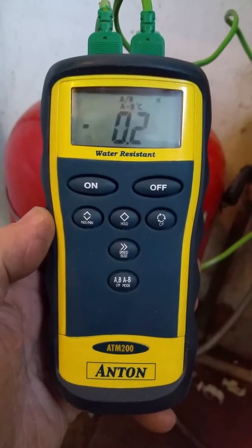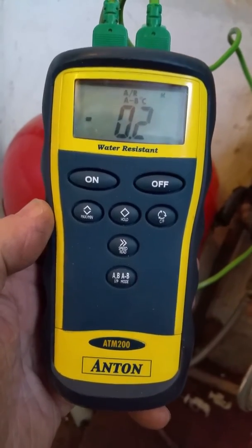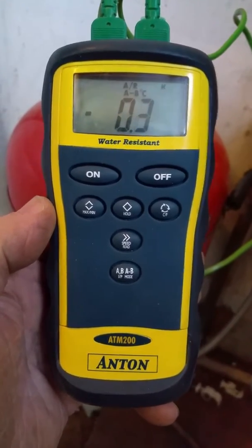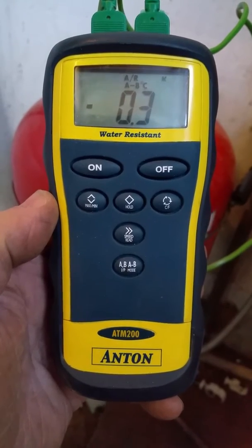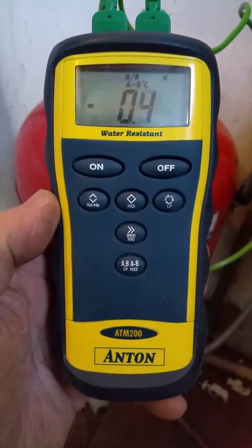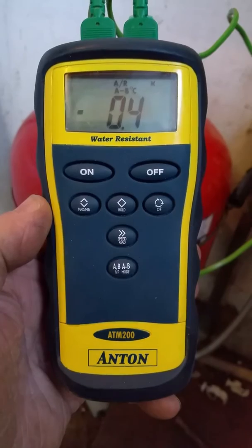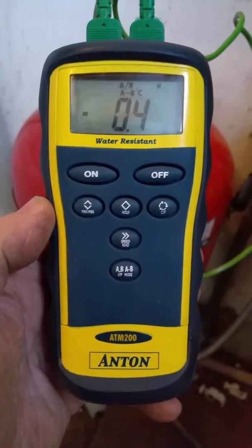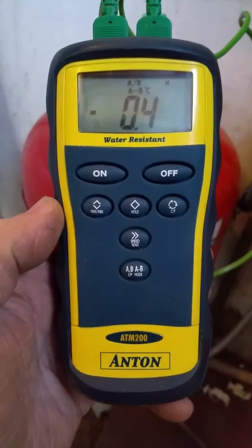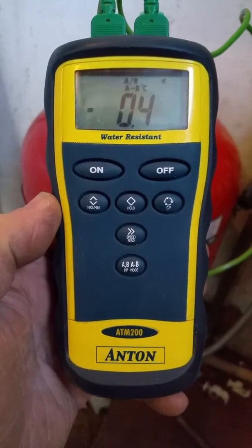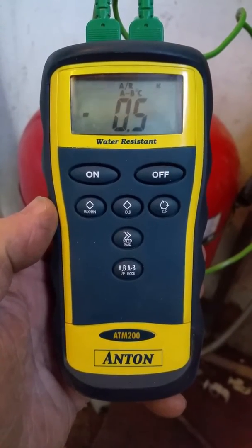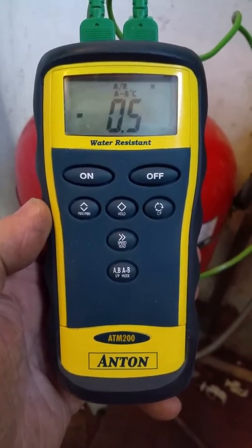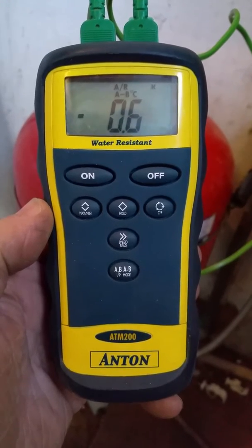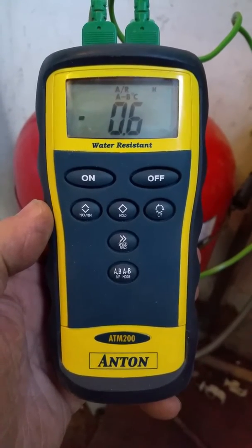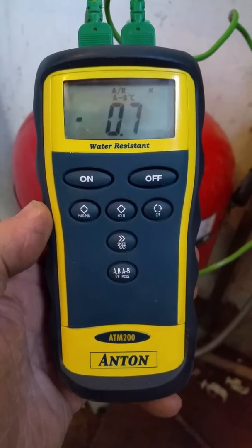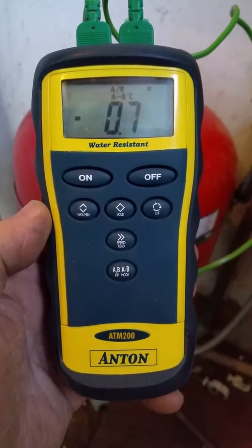So the temperature difference from one flow to the other, we lose half a degree C through that plate heat exchanger, which I think is absolutely amazing. So okay, it's day 1, it's the first time we've fired it, everything's absolutely clean, system's clean, boiler's clean. I'm sure we'll lose some efficiency of that over time as the plate gets dirty, but with regular servicing we can clean that up once a year, bring it back to new, just pop some FX2 in there, and we should get a good result.